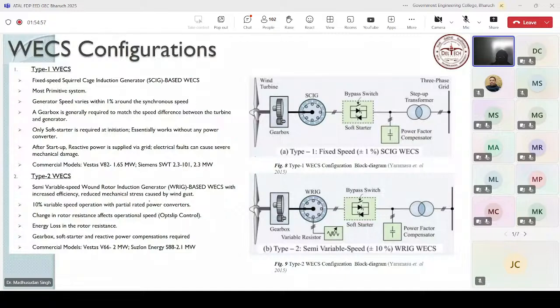So if a rotor side 3-phase winding is there, you have a provision to insert resistance in the rotor, and hence they control the rotor current, and that way you can control the turbine speed also to some extent. That's why a variable speed up to 10% you can control with rotor resistance. This happens to be, you can see, a very common arrangement in slip ring machines.